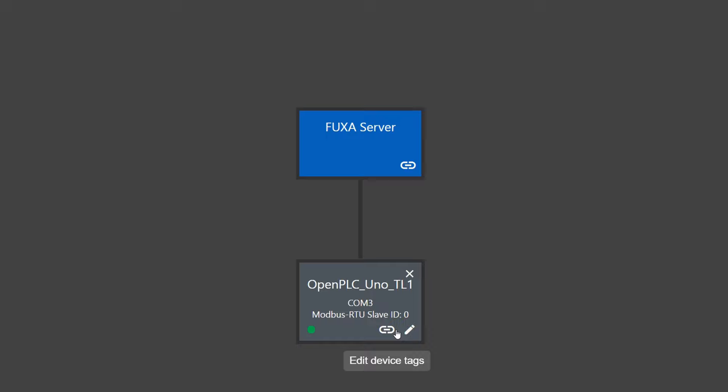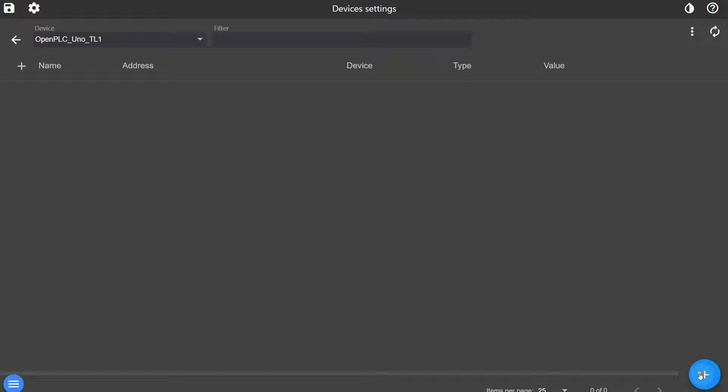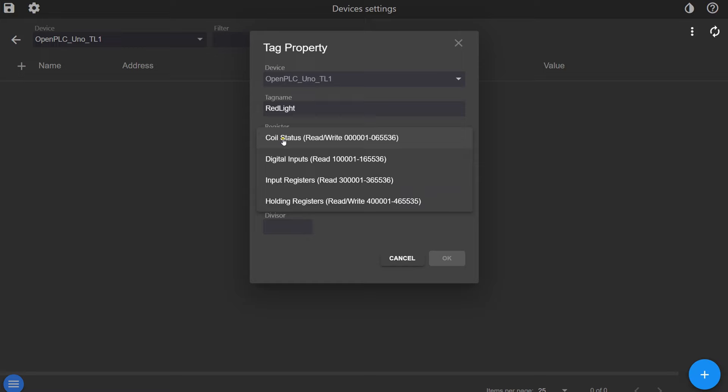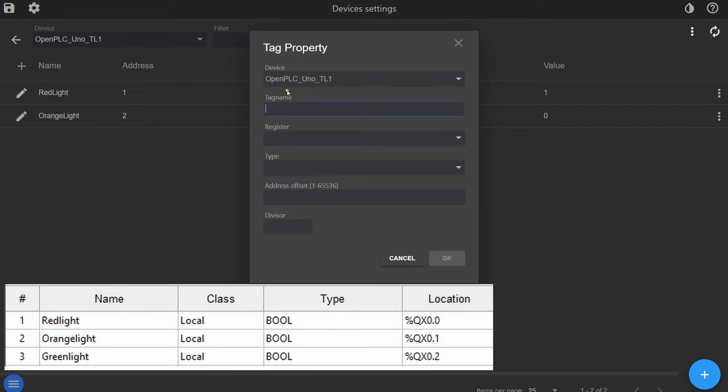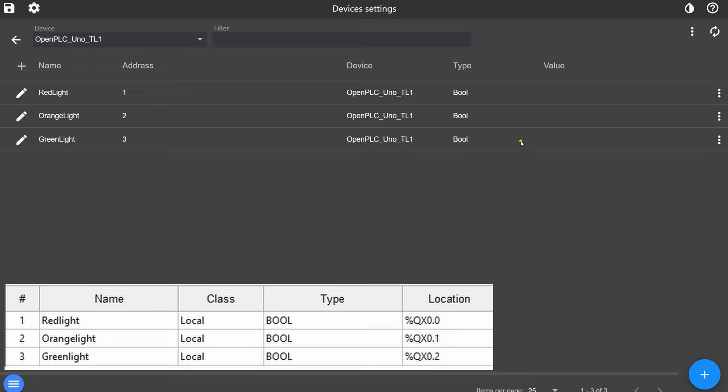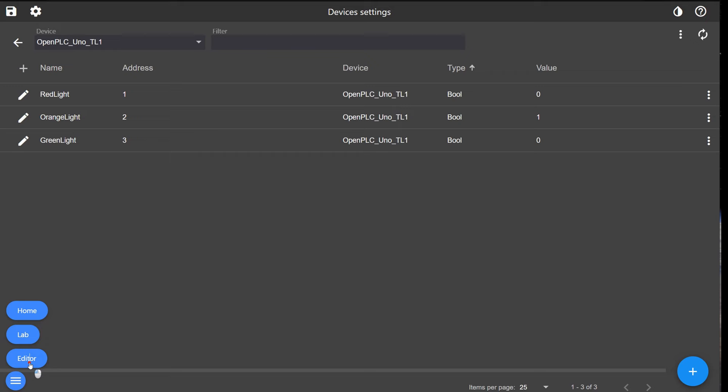The next step is to add the device tags to Fuxa. We first start by adding the outputs of the traffic light. These outputs are written in the coil status register. After adding the tags, you can immediately monitor the values. However, it can cause a little bit of confusion because output QX 0.0 will have address 1 and output QX 0.1 will have address 2 and so forth.